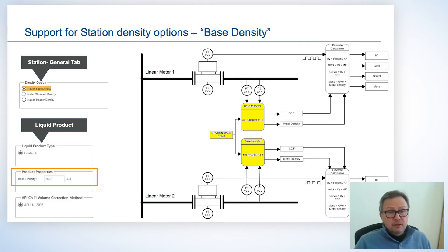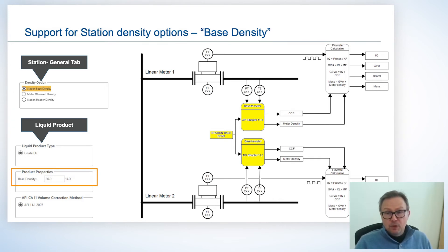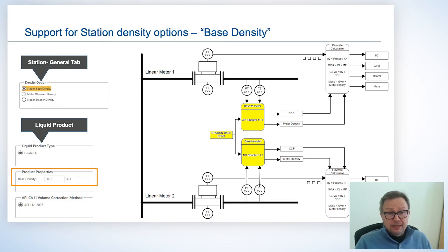Station base density means we have a user-entered station base density. It might get updated periodically by SCADA or manually, but we start with a base density. We then use the API Chapter 11 calculations to calculate what the meter density is — the density of the oil at meter pressure and temperature.